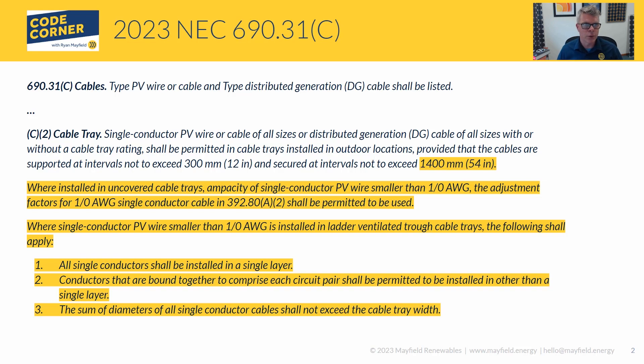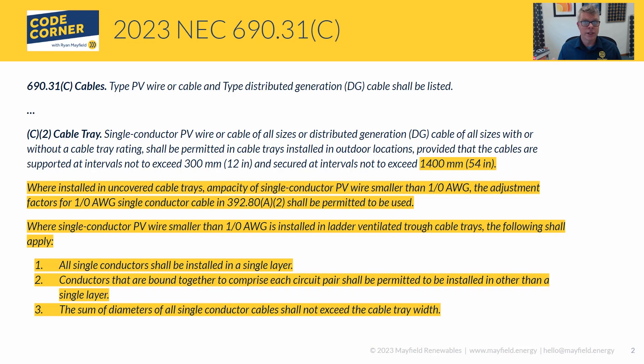690.31(C) talks about PV wire and cable shall be listed. Under C2, which is what I want to focus on, is about cable tray. That first charging statement under cable tray didn't really change — they just matched the style in terms of how they showed the units. The first part says we can use small conductors, PV wire, and DG cable of all sizes in cable tray. This was an important addition back in the 2017 version — the first time you could use small conductors in cable trays on rooftops.